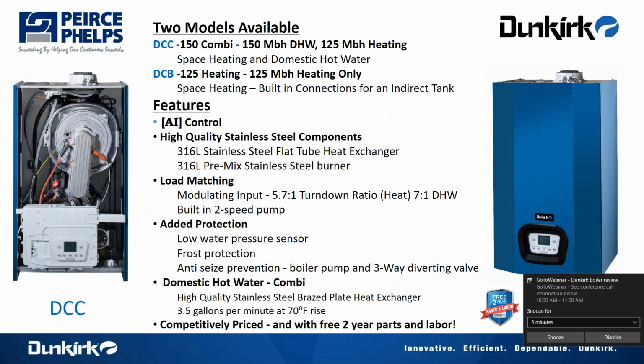We have the ability to load match. On the heat side, we're 5.7 to 1 turn down ratio. On the domestic hot water side, we're 7 to 1 turn down ratio. It's a built-in 2-speed pump that bounces back and forth depending on flow and demand. We have some added protection of limit controls, certainly. But in lieu of a low water cutoff, we have a low water pressure sensor that will stop the boiler when it stops seeing below 6 pounds of pressure, assuming that it's running out of water. There's frost protection on it. Also, pump exercising and diverting valve exercising in the off cycle every 24 hours.